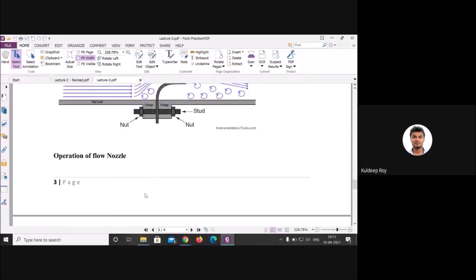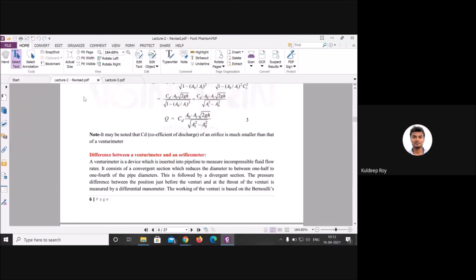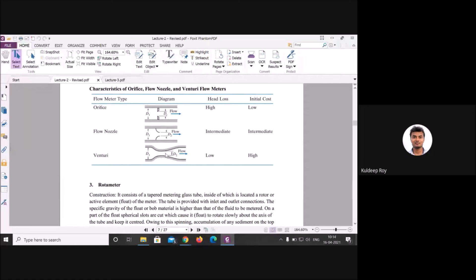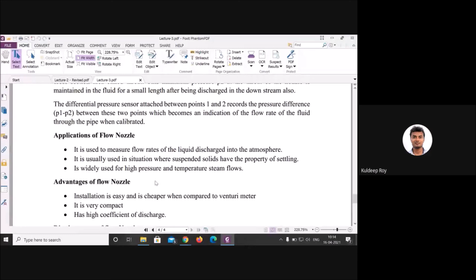Now if you are talking about the application of the flow nozzle, it is used to measure the flow rate of liquid discharged into the atmosphere. It is usually used in situations where the suspended solid has the property of settling, meaning if you have a suspension with solid particles, then only you can apply such a system. In the case of a venturi, if you have suspended solids, it is not good to use because the throat gets choked, depending on your diameter. So it is better to use the nozzle, which is widely used for high pressure and temperature steam flows.